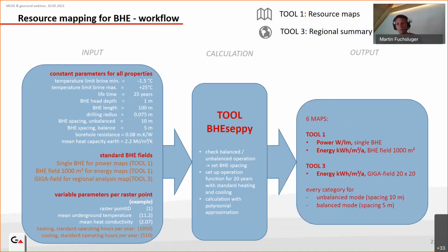Yes, and the outputs at the end are 6 maps for tool 1: 4 maps which give the power for single borehole heat exchangers, for balanced and unbalanced mode, and the energy for a 1000 square meter field, also for balanced and unbalanced mode.